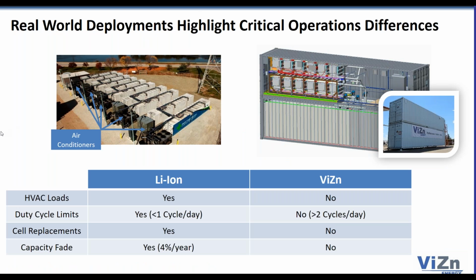So I don't know how many people on the phone have ever seen an image of a large-scale lithium-ion installation. There's one right up here in the upper left. What you'll see is that in addition to the containers, you have at the end of every container a power conversion system, and then you have the HVAC, right? These HVAC systems pump through insulated tubes into ducts throughout the containers, cooled air at rates driven by control systems looking at the internal ambient temperature and surface level temperature of the cells and modules themselves. It's highly regulated. In warm climates, they can run 24/7, frankly, depending upon the use case and duty cycle. And just one heads up, typically these AC loads, these HVAC loads, are never included in the round-trip efficiency calculations.